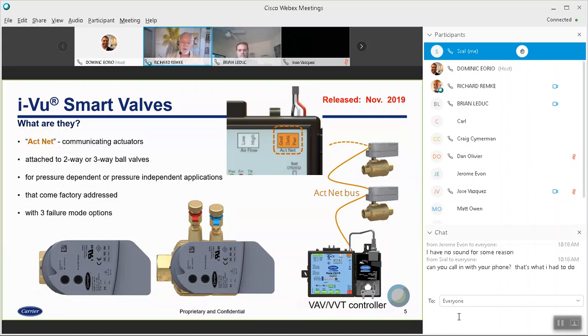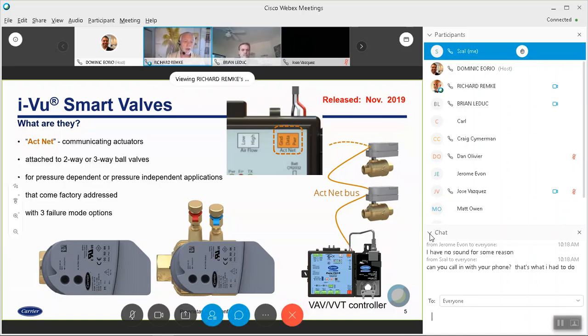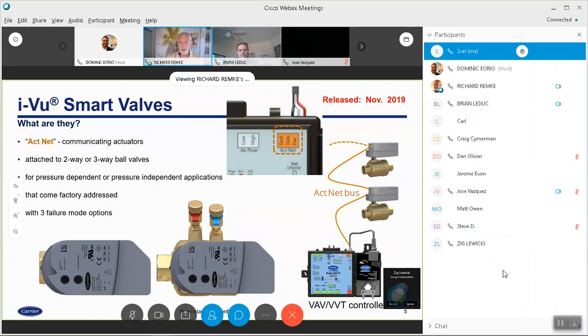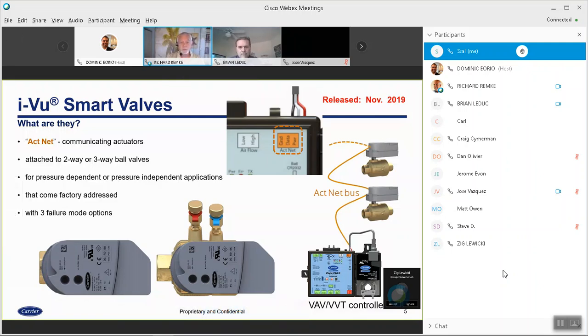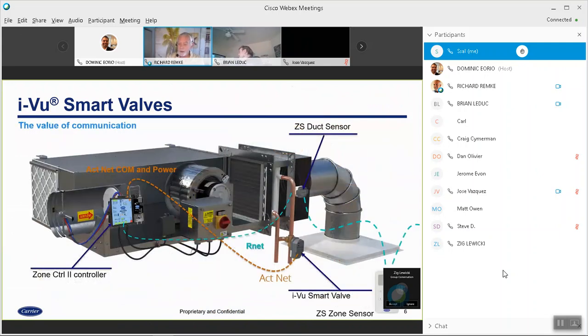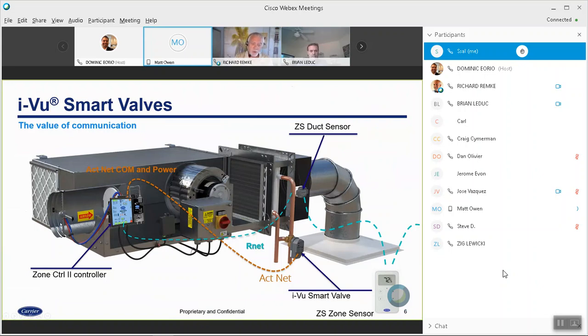They come in two-way and three-way ball valves. We have pressure-dependent and pressure-independent applications. They come factory addressed, so you can just plug and play. And they have 3 different failure mode operations. And the power of it is the ability to have a communicating actuator network on the zone controller.